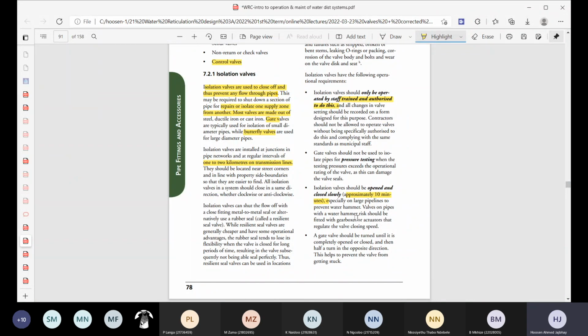And it's common. Those of you that live in Itigwini often find that you have a burst pipeline on the road somewhere, and somebody comes in to repair it. Once they've done the repairs, they will open up the valve so that everyone can get water again. If the person doing that is not trained, you'll see 2 or 3 days later you'll have to call them out again, because there'll be more burst sections on that pipeline. The reason you have this problem of more burst sections is because there was water hammer in the pipeline when they opened that valve.